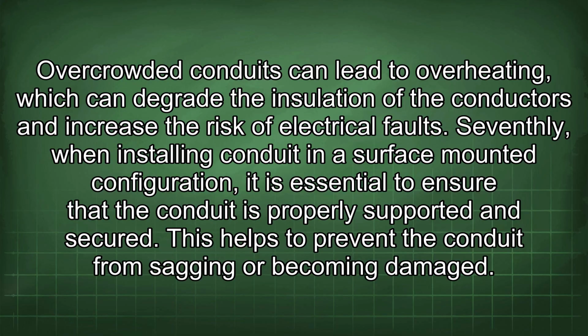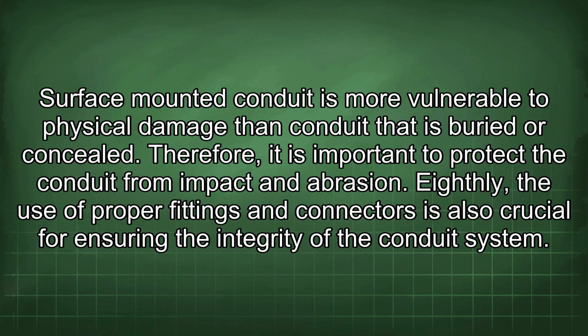Seventhly, when installing conduit in a surface-mounted configuration, it is essential to ensure that the conduit is properly supported and secured. This helps to prevent the conduit from sagging or becoming damaged. Surface-mounted conduit is more vulnerable to physical damage than conduit that is buried or concealed. Therefore, it is important to protect the conduit from impact and abrasion.